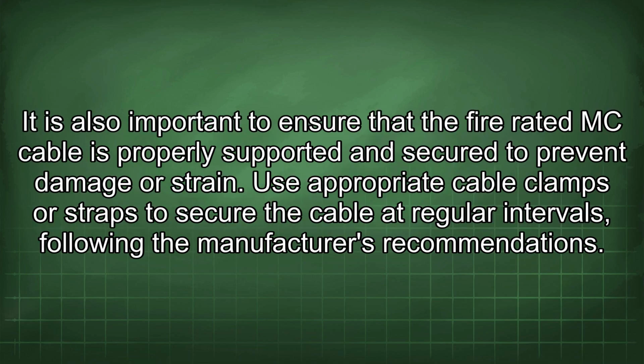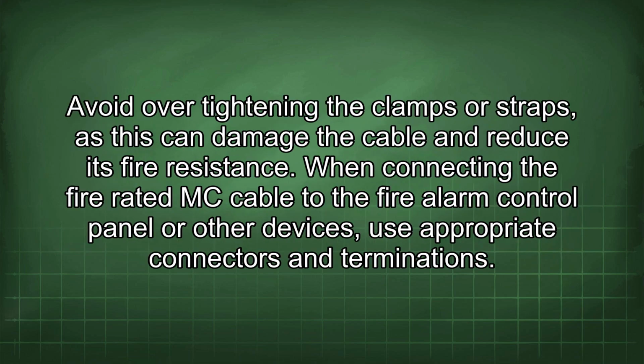It is also important to ensure that the fire-rated MC cable is properly supported and secured to prevent damage or strain. Use appropriate cable clamps or straps to secure the cable at regular intervals, following the manufacturer's recommendations. Avoid over-tightening the clamps or straps, as this can damage the cable and reduce its fire resistance.